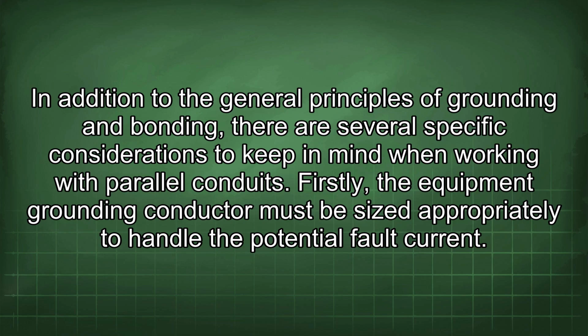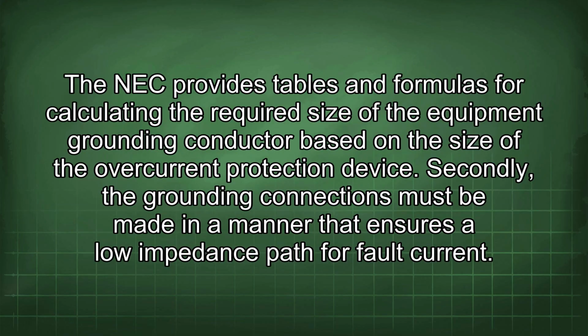In addition to the general principles of grounding and bonding, there are several specific considerations to keep in mind when working with parallel conduits. Firstly, the equipment grounding conductor must be sized appropriately to handle the potential fault current. The NEC provides tables and formulas for calculating the required size of the equipment grounding conductor based on the size of the overcurrent protection device.